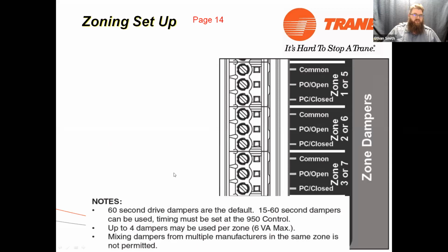I did mention that you can use other brands of dampers. It defaults to a 60-second travel damper. That's the time that it takes to go from fully open to fully closed. You can adjust that damper timing to use other dampers. There are some Carrier systems out there that use 15-second dampers. As long as that is somewhere between 15 and 60 seconds and all the dampers are the same, you can use that third-party damper. You may just have to adjust that timing.